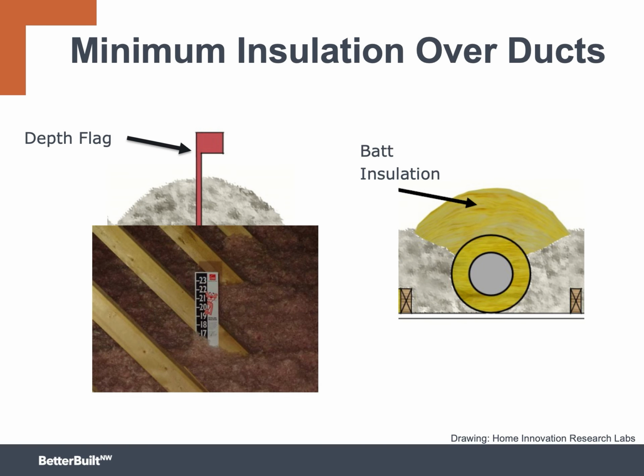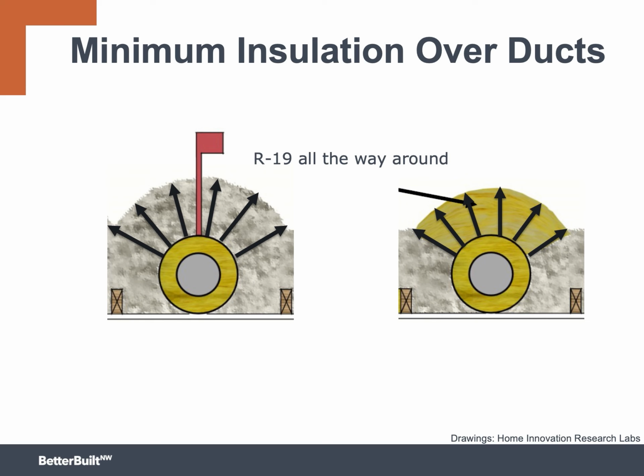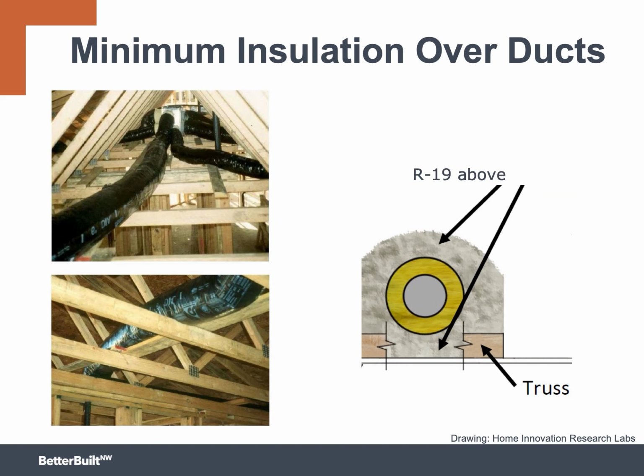How can you and the building inspector verify that you have sufficient insulation depth? Here are 2 options. First, you could install insulation rulers or depth flags so the exact depth of the insulation can be seen at a glance. Second, you could place R19 fiberglass batts over the ducts and blow loose insulation to fill in around the sides. The key is that there's at least R19 insulation on the top and around the sides along the entire length of ductwork. Of course, when ducts run perpendicular to the joists or truss members, they will not touch the ceiling, so insulation will have to be piled up around the ducts even higher in order to get the right amount of material over the top.